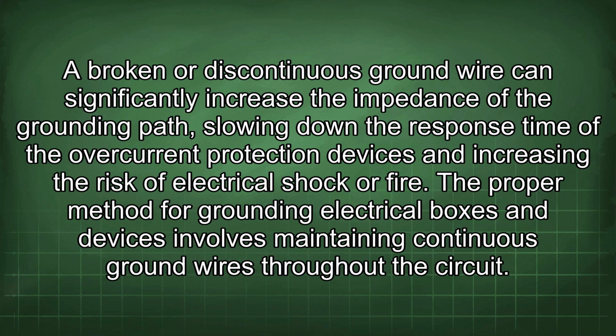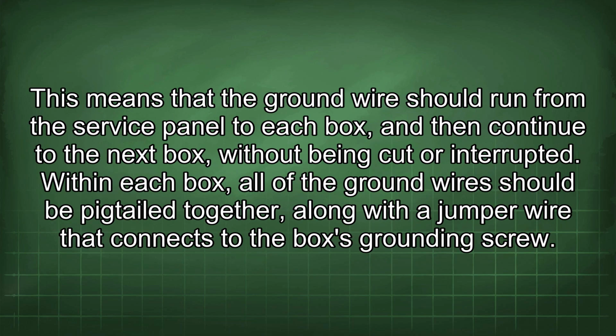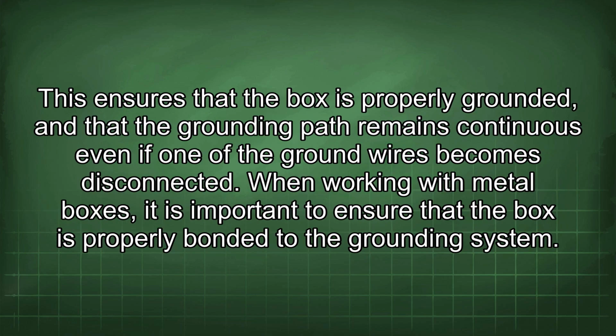The proper method for grounding electrical boxes and devices involves maintaining continuous ground wires throughout the circuit. This means that the ground wires should run from the service panel to each box, and then continue to the next box, without being cut or interrupted. Within each box, all of the ground wires should be pigtailed together, along with the jumper wire that connects to the box's grounding screw. This ensures that the box is properly grounded, and that the grounding path remains continuous even if one of the ground wires becomes disconnected.